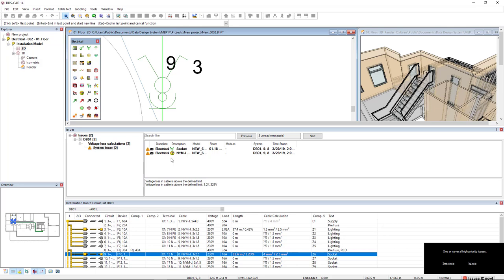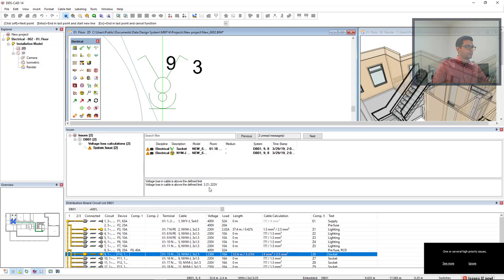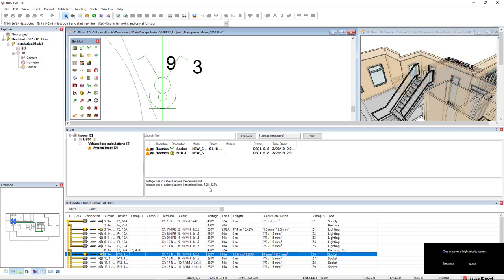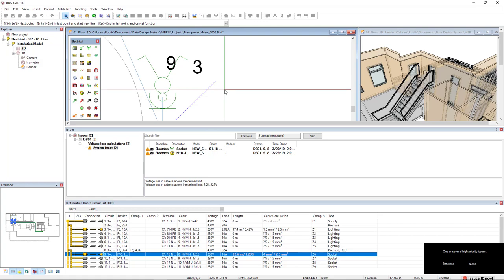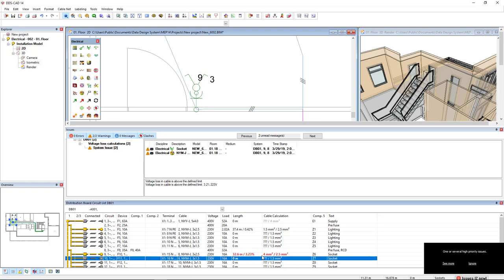Now we have this issue showing the information that voltage loss in cable is above the defined limit. The limit in this case that we did not see is 3%, and right now we have 3.2%. I still have the function activated, so I will press escape. We can come here to the circuit list and we see the information in red.